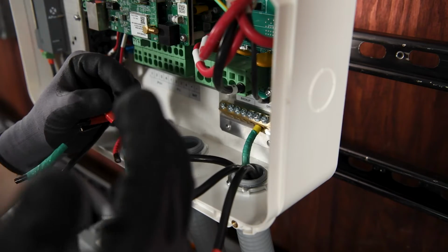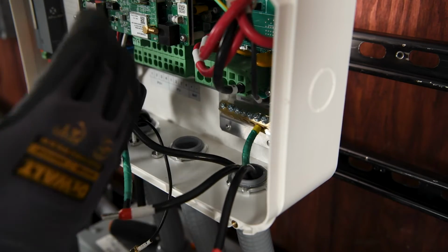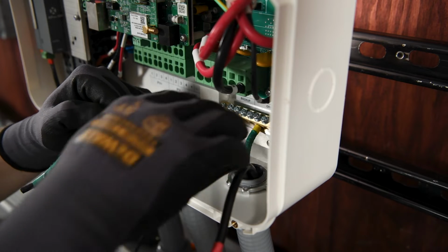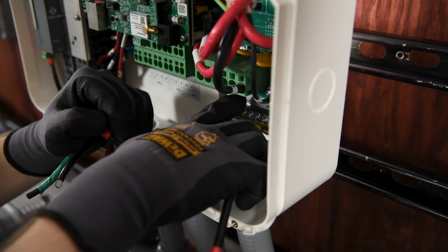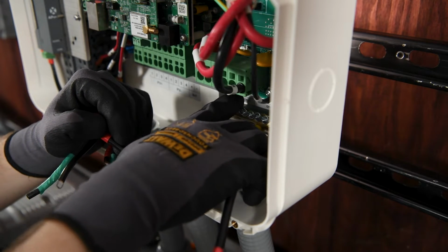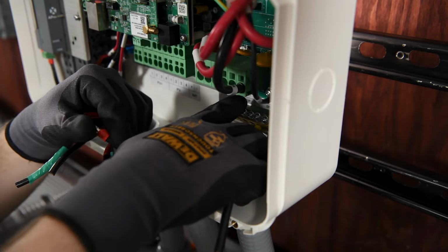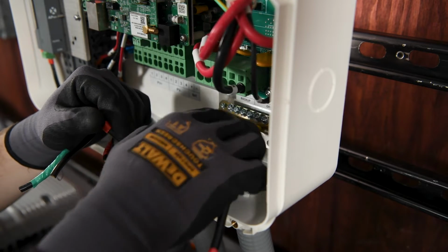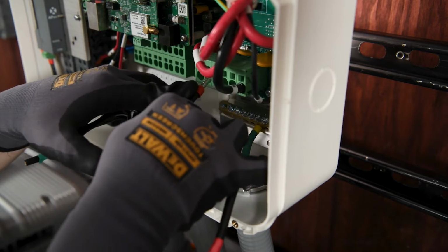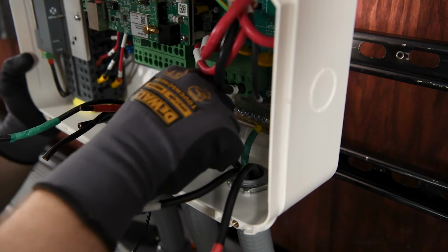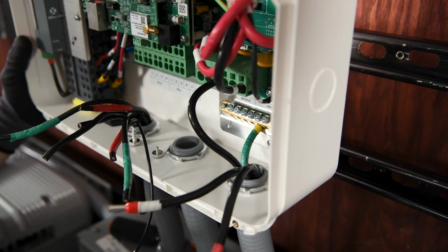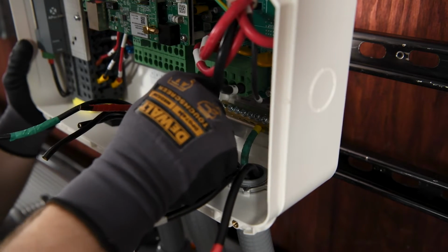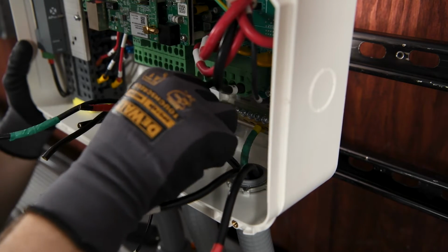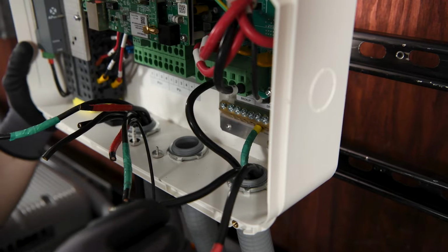So next we're going to connect our hot conductors, our leg 1, neutral, and leg 2. At the bottom right under the terminal block, you'll see the backup and grid connections. Again, when we're operating with the SYN, we want to use the grid connections. So I'll take the black conductor and I will connect it to the L1 terminal block. Now, again, do a quick pull test, ensure that it doesn't have any loose connections or that it's not going to come out of place.